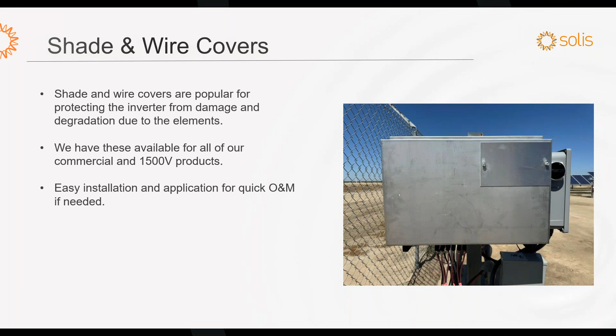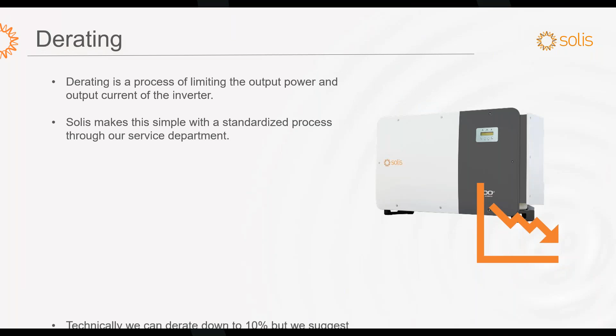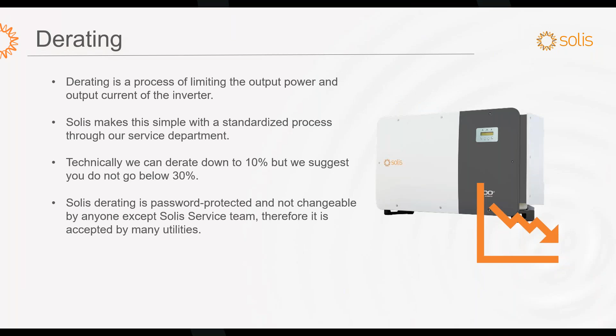We also offer derating. As you guys are familiar with, many utilities are requiring this to limit the output power and current of the inverter. We have a standardized process through our service department that helps ensure that your products are rated at the required level. We really do not recommend going below 30%. And then, of course, it's not changeable. It's password protected and accepted by many utilities. We do provide a Solis approved letter as well as new labels for the products that are derated through this process.